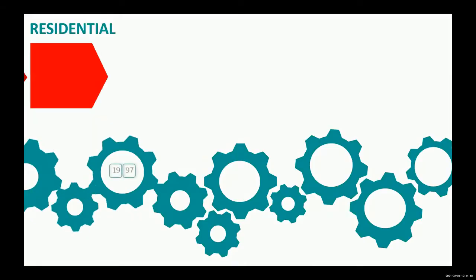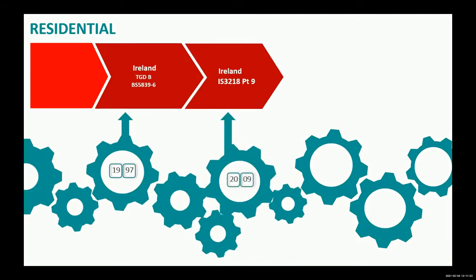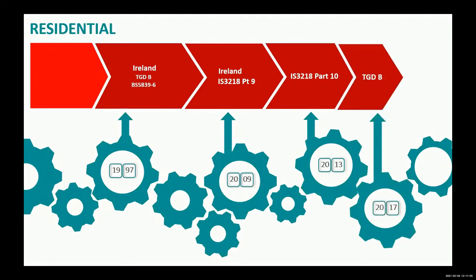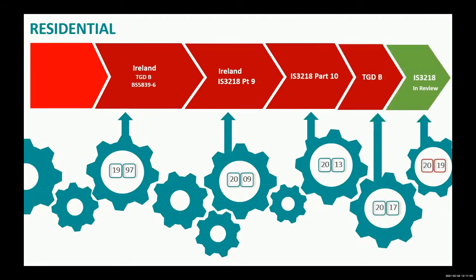Okay, so just to start off on the standards and regulations, when they came into play in Ireland was in 1997 under Technical Guidance Document B, and that referenced the BS 5839 Part 6. Then we moved on in 2009. We developed our own standards in relation to residential detection under IS 3218 Part 9. In 2013, again, there was a refurb of IS 3218, and it was moved out to Part 10. And then in 2017, it was the first time Technical Guidance Document B referred to the IS 3218 standard, which brought our own Irish standard into play here, and that's the Part 10, and that's where we're at the moment.